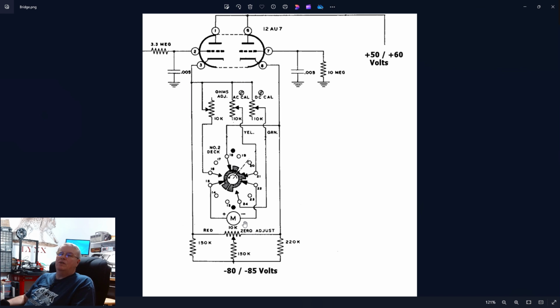The meter can be switched into series with different adjustments. So we can calibrate our DC here, we can calibrate our AC here, we can calibrate our ohms here, and they don't affect each other. By what range we choose, what mode we select, we shift in the right calibration right here. That's the purpose of it. So hopefully I've made that clear what's going on with this switch, the meter, and here.